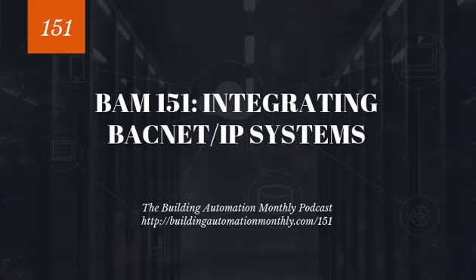Each BACnet network, which is synonymous with subnet, needs to have a BBMD with a BDT. And that BDT, that broadcast definition table, or distribution table, one of the two, needs to have the subnet address, or the device address of the BBMD for that specific network. That way those broadcasts can be shared.